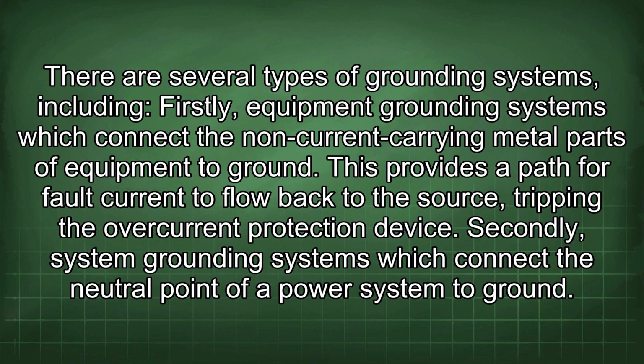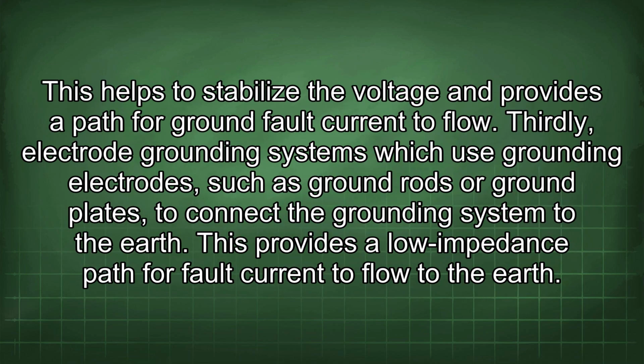There are several types of grounding systems, including, firstly, equipment grounding systems which connect the non-current carrying metal parts of equipment to ground. This provides a path for fault current to flow back to the source, tripping the overcurrent protection device. Secondly, system grounding systems which connect the neutral point of a power system to ground. This helps to stabilize the voltage and provides a path for ground fault current to flow. Thirdly, electrode grounding systems which use grounding electrodes, such as ground rods or ground plates, to connect the grounding system to the earth. This provides a lower impedance path for fault current to flow to the earth.